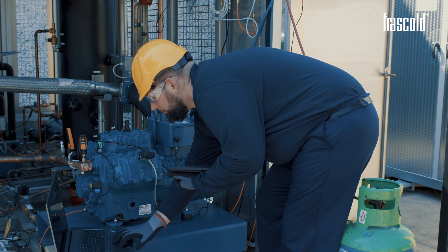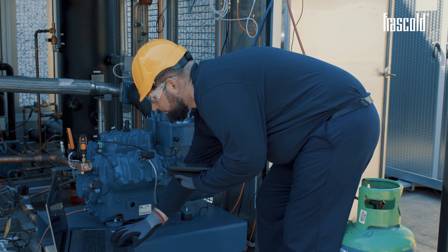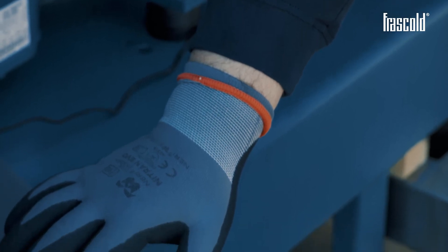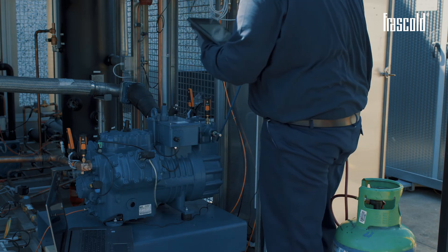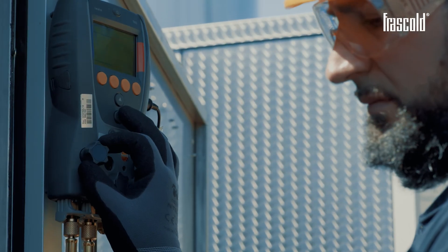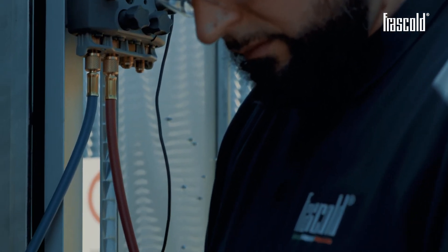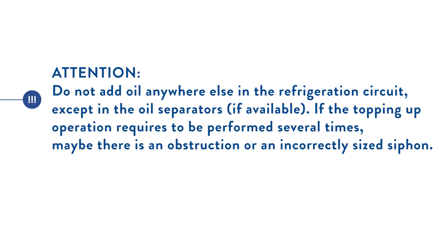Keep the oil level under control. If it falls below the minimum level, more oil may need to be added. In this case, stop the compressor, close the valves, recover the gas contained in the compressor, and pour the oil into the appropriate inlet. At the end of the topping-up operation, vacuum the compressor and reopen the valves. Do not add oil anywhere else in the refrigeration circuit except in the oil separators if available. If the topping-up operation requires to be performed several times, maybe there is an obstruction or an incorrectly sized siphon.